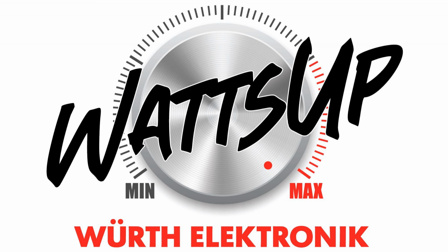but I'm not really improving anything. So if I close everything, for instance, and we do a measurement of EMI in 1 second, I upload, I go in EMI, I put the line with a quasi peak, I would say that it passes. And this is with filter number 2, the small filter. I'm freezing it, I open another one, I measure the same with a quasi peak, and I put filter number 1, the big filter.